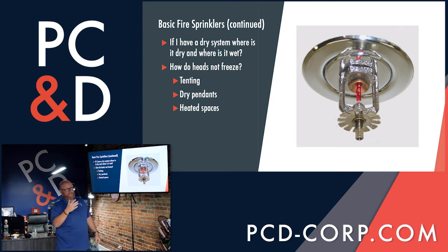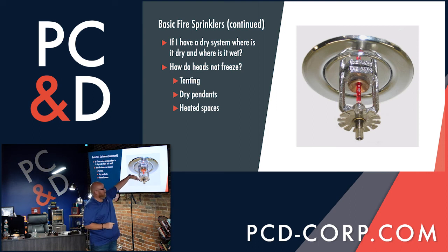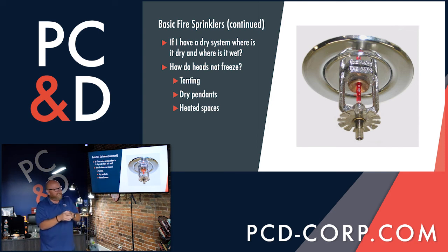If you remember from our slides a couple minutes ago, water is designed to be at that head within 30 seconds, okay? Now all of a sudden you've got water spraying down, water spraying on this little star-like device on the front of it. That star-like device, yet again, is engineered and designed for a purpose and a function. As the water comes down, it disperses the water, almost making like an umbrella, where you're literally sprinkling like a U-shape type thing upside down.